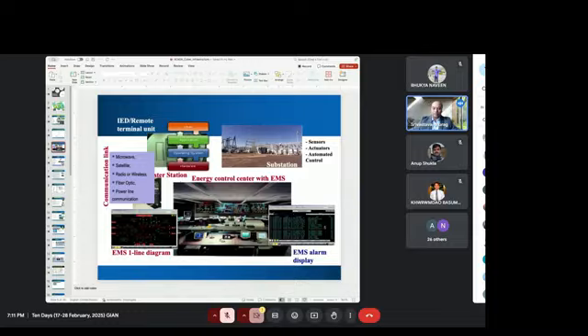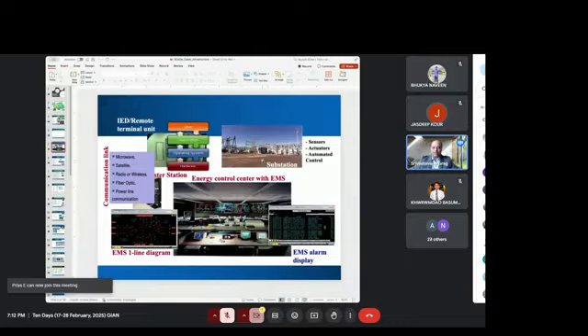There we put the switch yard, a small control room, all these IEDs, and some kind of merging unit now, which was not done in the past. A merging unit basically takes a lot of digital inputs and integrates them into some digital format, so it can be transferred easily and you can avoid electric wire. So the merging unit is the way to avoid a lot of wires in the substation.